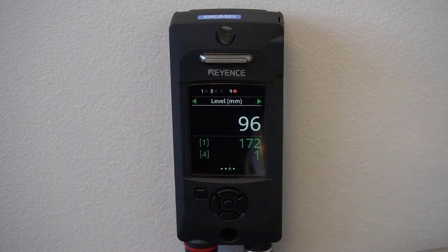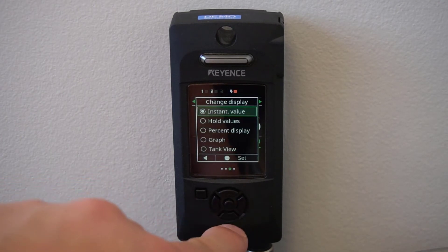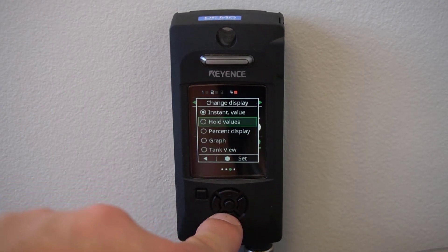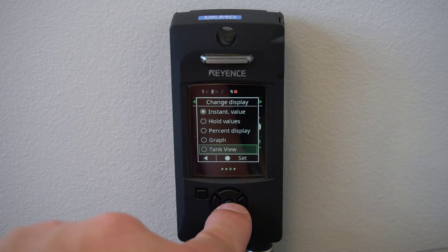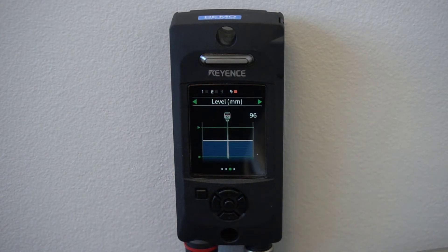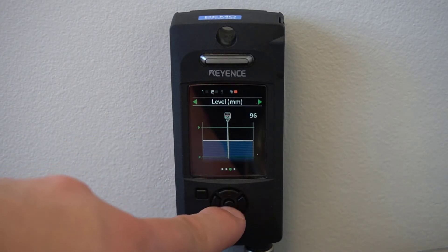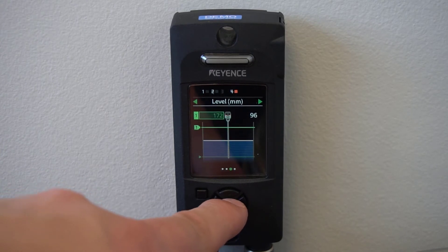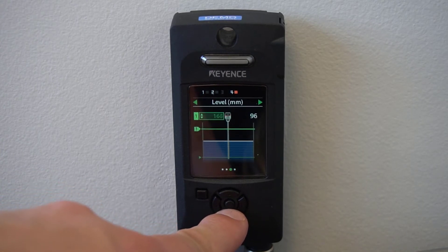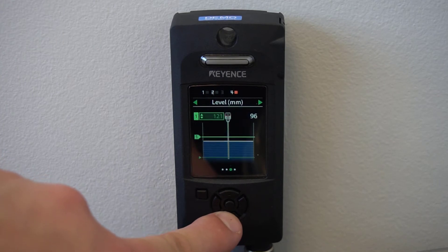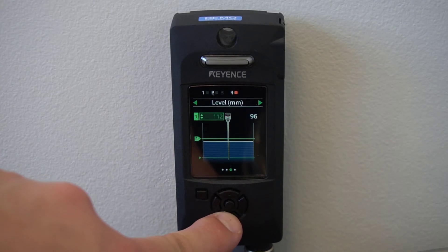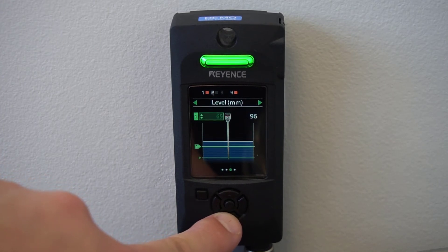Using the easy-to-read intuitive display of the FI-1000, we can simply set up the FL level sensor by tapping the center button and going down to what's called tank view. This gives a great visualization as to what the FL level sensor sees. The current value can be seen on the top right corner of the screen at 96. If we tap the down button, we can see the current setting value at 172 millimeters. Here we can use the down arrow key to bring that number below our current value to turn on the output.